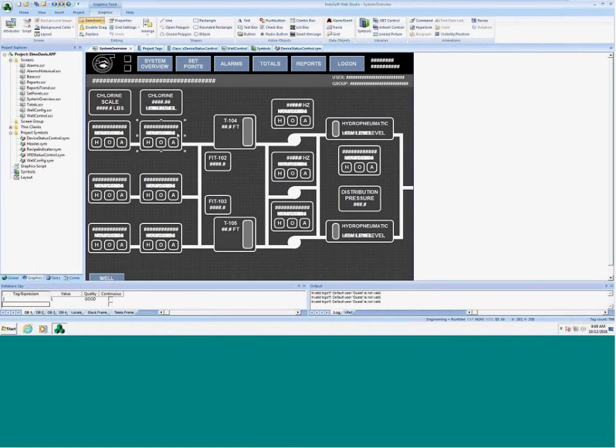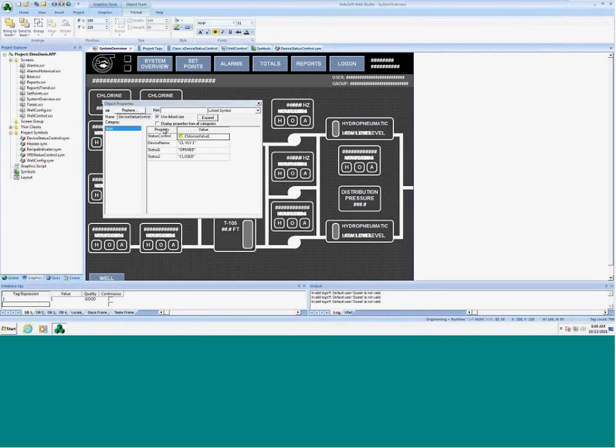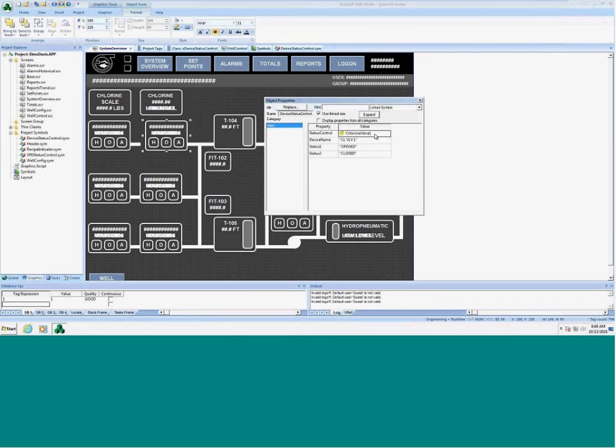So this, unlike that other screen, is one single device, one single object. And it's got custom properties that I created. I pass in a status control, a device name, status 1 and status 2, which are just strings. This device name is just what gets displayed up top here, and for status, I wanted different verbs for different statuses for different devices, so I allowed that to be modifiable from here.